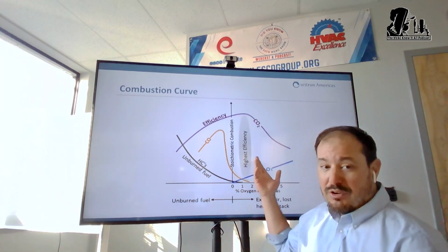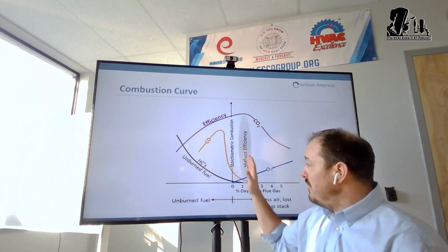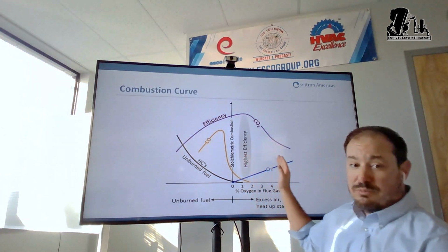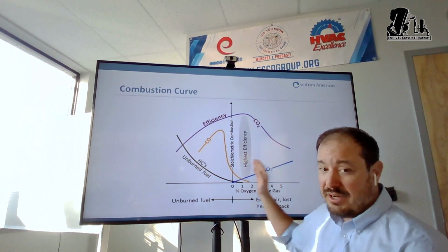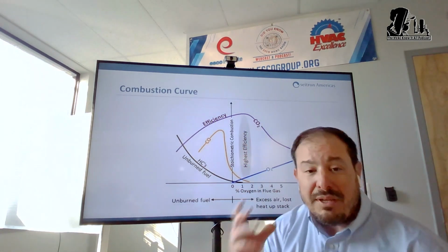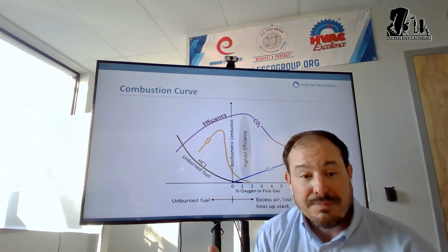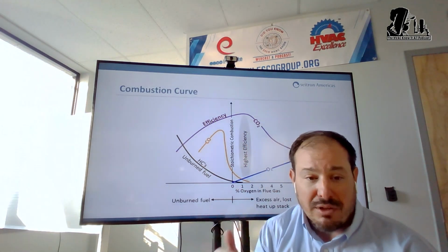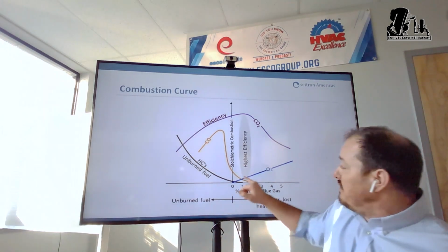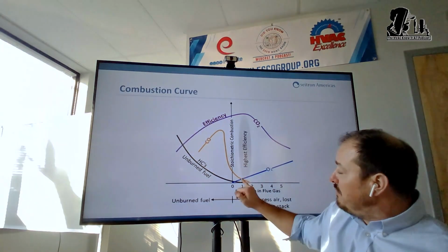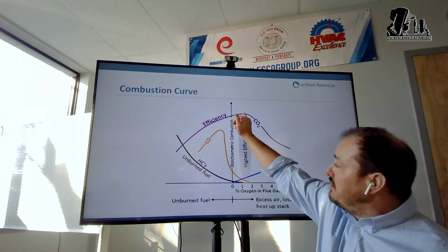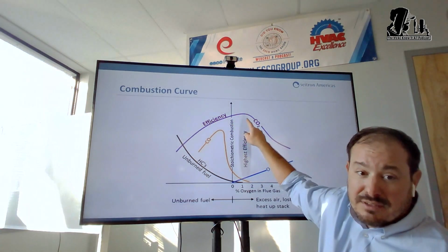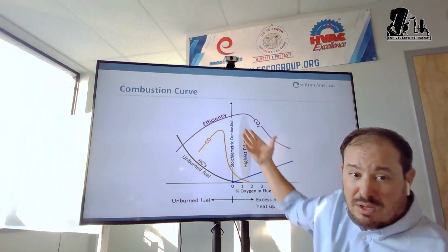Exactly. But if you notice the curve, it's just barely on the air-rich side, not too much, because we don't want too much air. But that's what we call the highest efficiency range. And if I get that boiler, furnace, or water heater to get my CO at a certain number and my oxygen between a couple numbers, my CO2 will be at its peak, if you notice, and my efficiency will be at its peak while it's running safely.